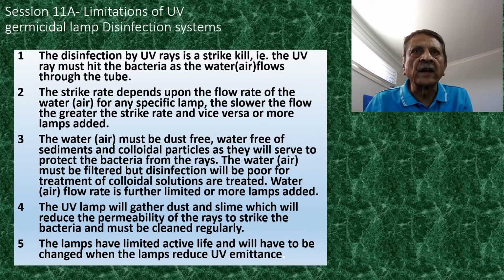The water or air must be dust-free. If water, free of sediments or colloidal particles, as these will serve to shield the bacteria from the rays. The air or water must be filtered, but disinfection will be poor for treatment of colloidal solutions. The water or airflow rate is further limited, or more lamps have to be added.